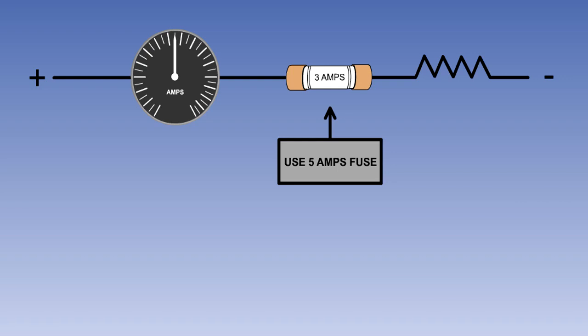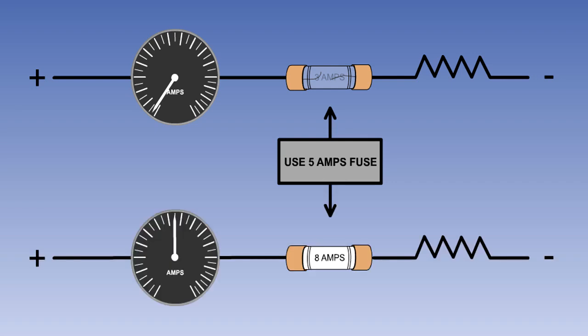It is important always to replace a fuse with one of the correct rating. Using a replacement fuse of a lower rating will cause it to blow prematurely. While using one with a higher rating will leave the circuit vulnerable to excessive current and the subsequent risk of overheating.